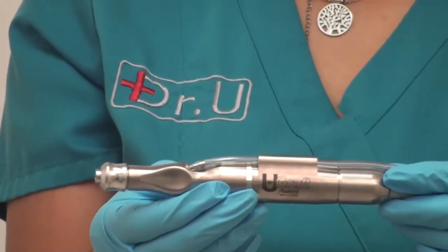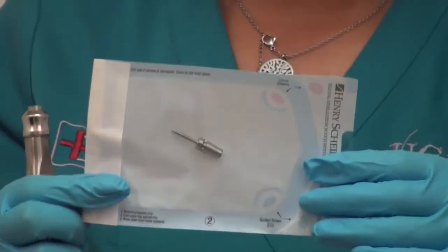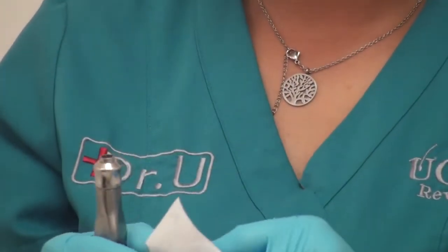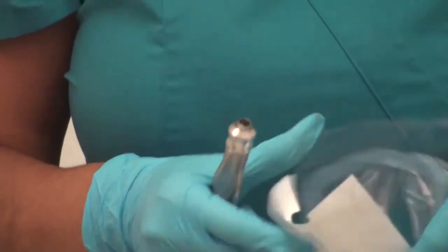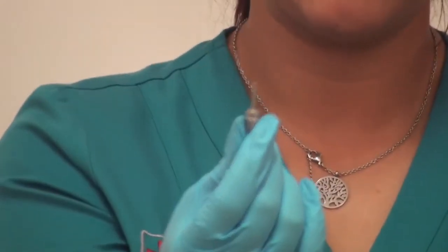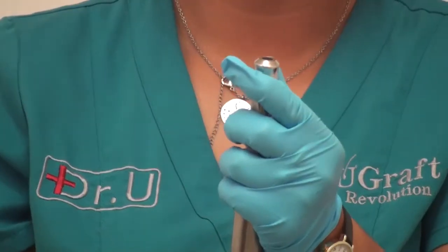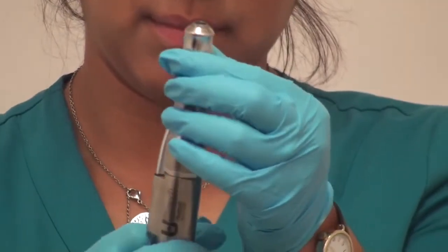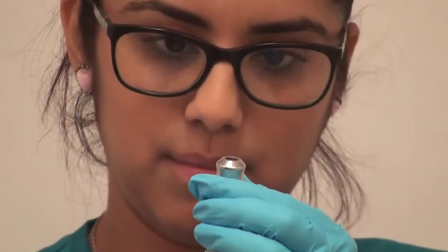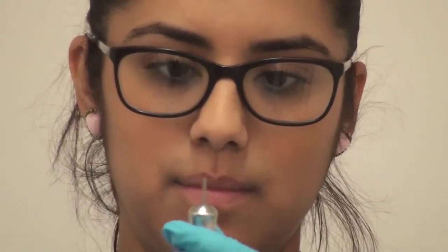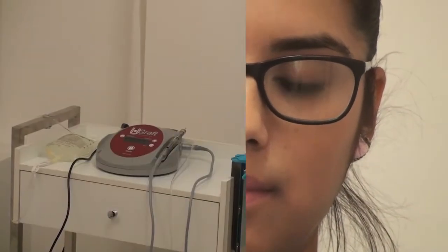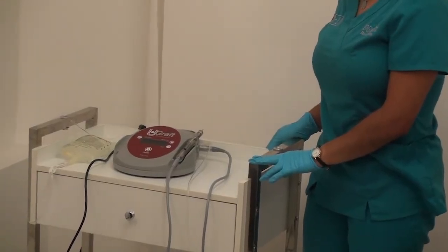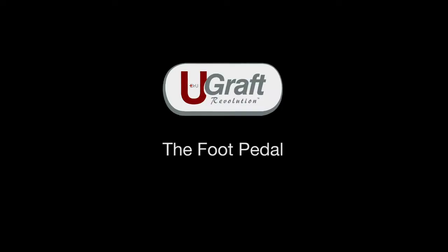Next, connect the intelligent punch to the handpiece. The punch has been sterilized at this point by using your choice of sterilization method. Remove the punch from the sterilization bag and put it into the handpiece, as demonstrated on this example, by first pushing up the mobile collar at the end of the handpiece. Push it up to release the ball bearings, which hold the punch to the handpiece collet. Put the punch into the collet while pushing up the collar. It should snap in very easily. Then pull back the collar until you hear a click that indicates that the punch is in place. Congratulations, you are now ready to operate the Dr.UGraft hair transplant system.